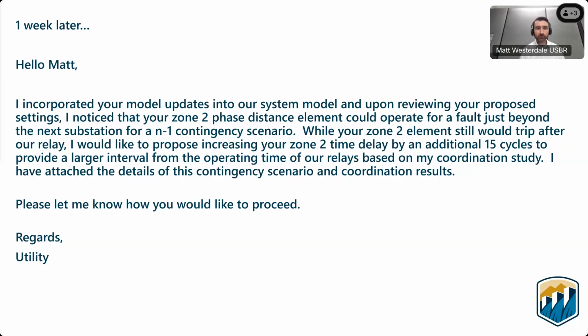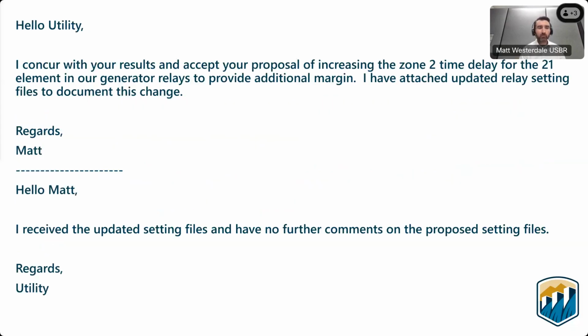So my response to the utility would be to perform the same evaluation that they did, see if I am able to replicate their results, and if their proposed change would cause any issues for me. In this case, their proposal to increase the zone 2 time delay I consider acceptable. So I updated my proposed relay setting files to document this change and sent it to them, so they have another set of final setting files that we're planning to implement.